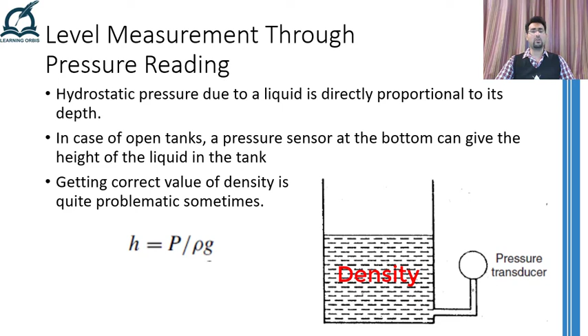In case where the containers are closed, a single pressure reading at the bottom will not give us the pressure which the liquid is exerting. Therefore, we need a differential pressure transducer that can sense the difference of pressure between the top and the bottom of the tank. Once again, we can use a similar formula to figure out the level of the liquid present in the container. Apart from the problem of figuring out the true value of the density of the liquid present in the container, another problem associated with these kinds of setups is leakage from the taps made at the bottom for pressure sensing.